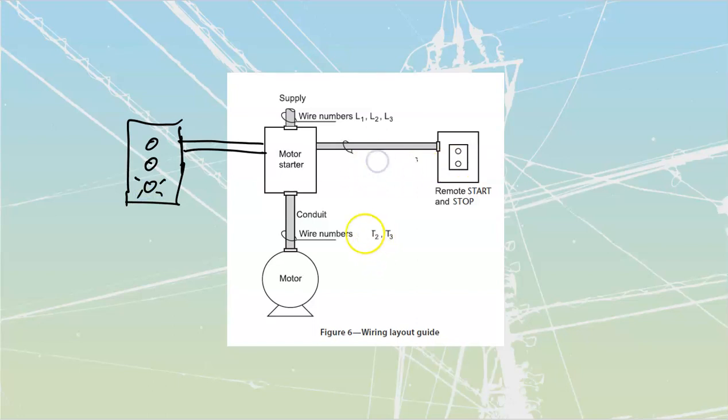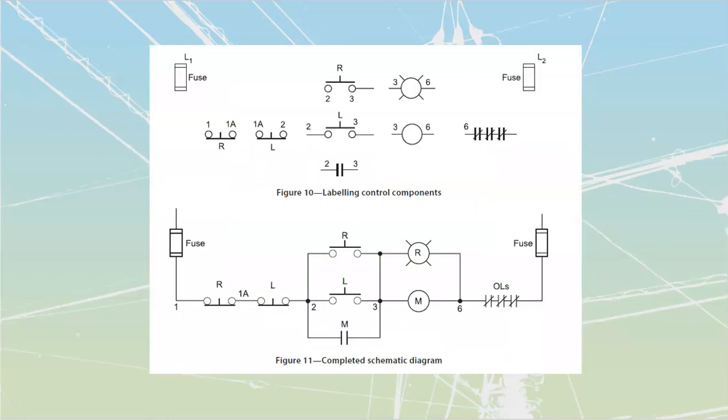Now what we need to do is figure out how many wires I'm going to pull inside of each of these conduits. It's a little bit difficult initially to sort this out until we lay out which components are inside of which one. We're just going to do that looping thing that we have, okay? I want to take a look at my components. Anytime that I'm doing the loop, I want to draw a bubble around all the components that are going to be inside of the same box.